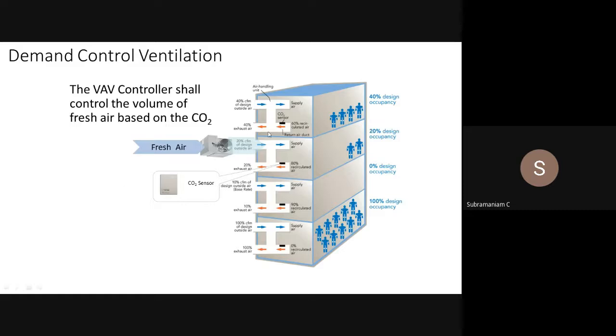Now, fresh air is something which is demand control ventilation. For example, you will find in this drawing, in this slide, that people in different floors, number of people are different. Initially when designing, we will design with 100% design occupancy. But 100% people may not be there in that particular area. Here, for example, only 4 people are there where I have designed for 10. So my fresh air requirement is only for 4, not for the entire 100. If I keep on pumping for all the 10 people or 100 people, then my energy consumption at the AHU will be very high. So that is why ASHRAE standard 90.1 talks about demand control ventilation.